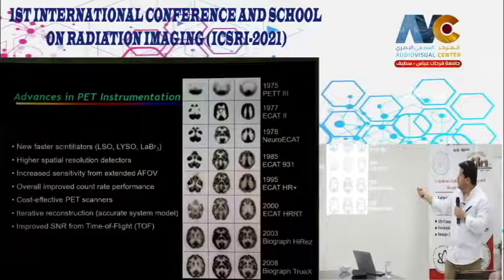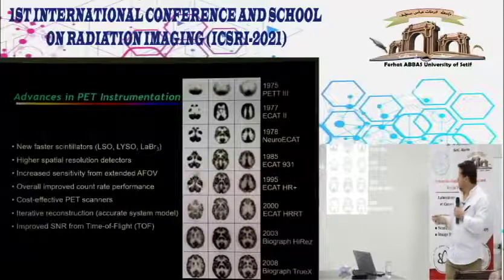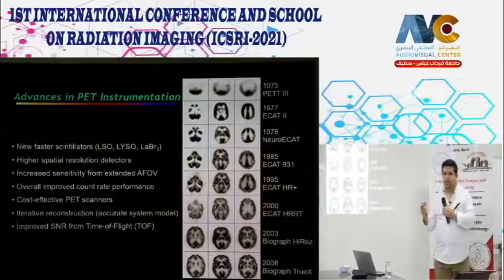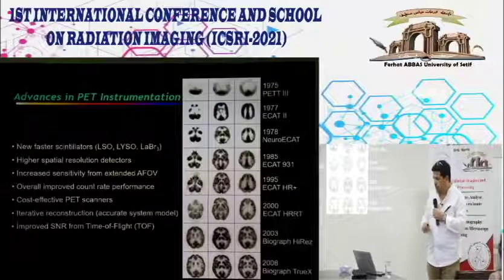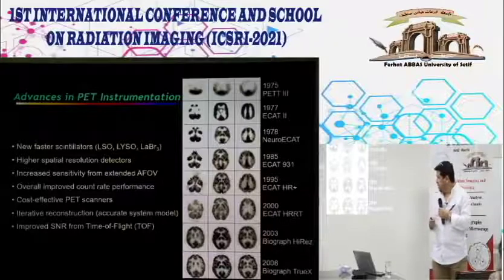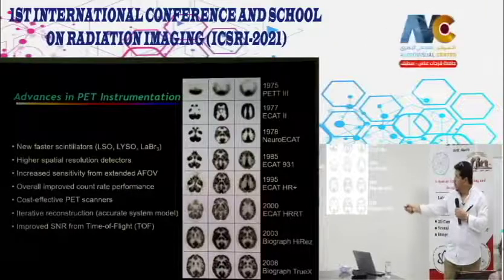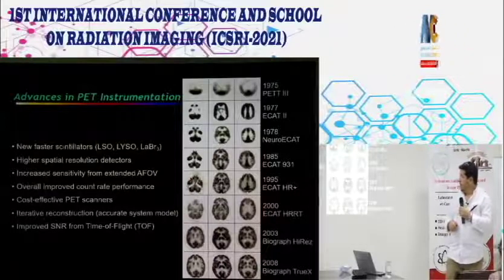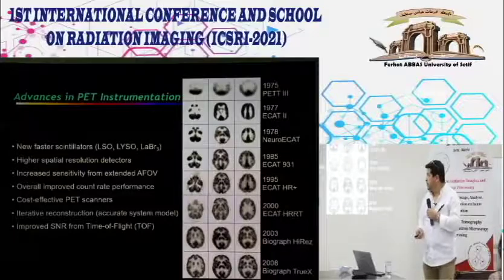The evolution of PET image quality: the 1970s systems had pixel sizes close to 1 cm (very low spatial resolution). Now spatial resolution is approximately 2–2.5 mm, achieved through improved scintillation crystals with higher stopping power, fast electronics, and advanced reconstruction techniques.